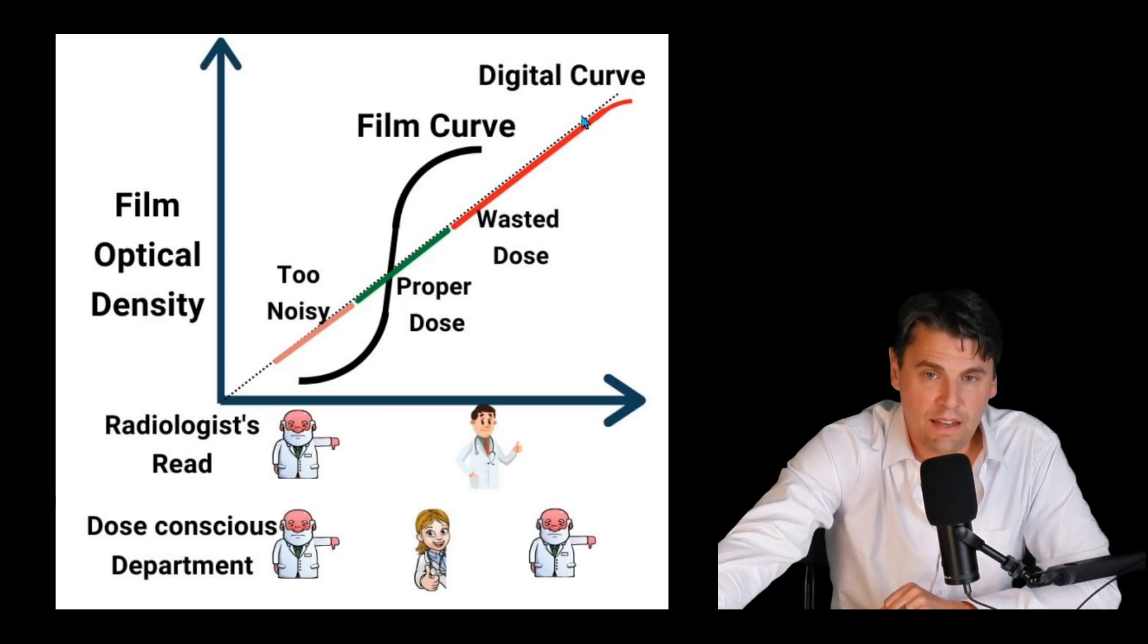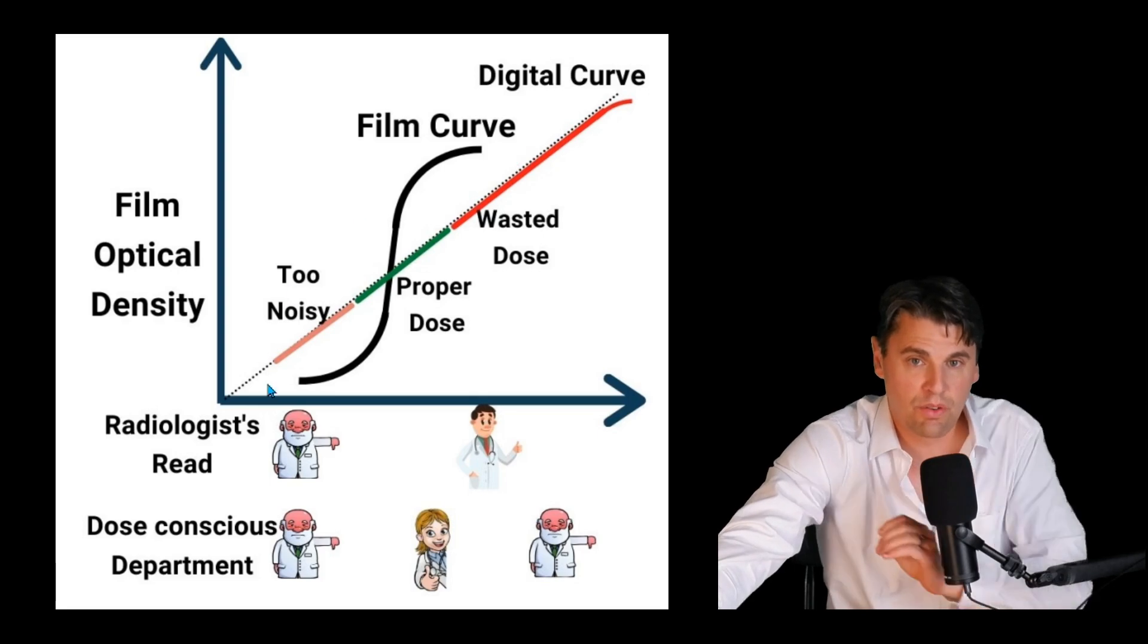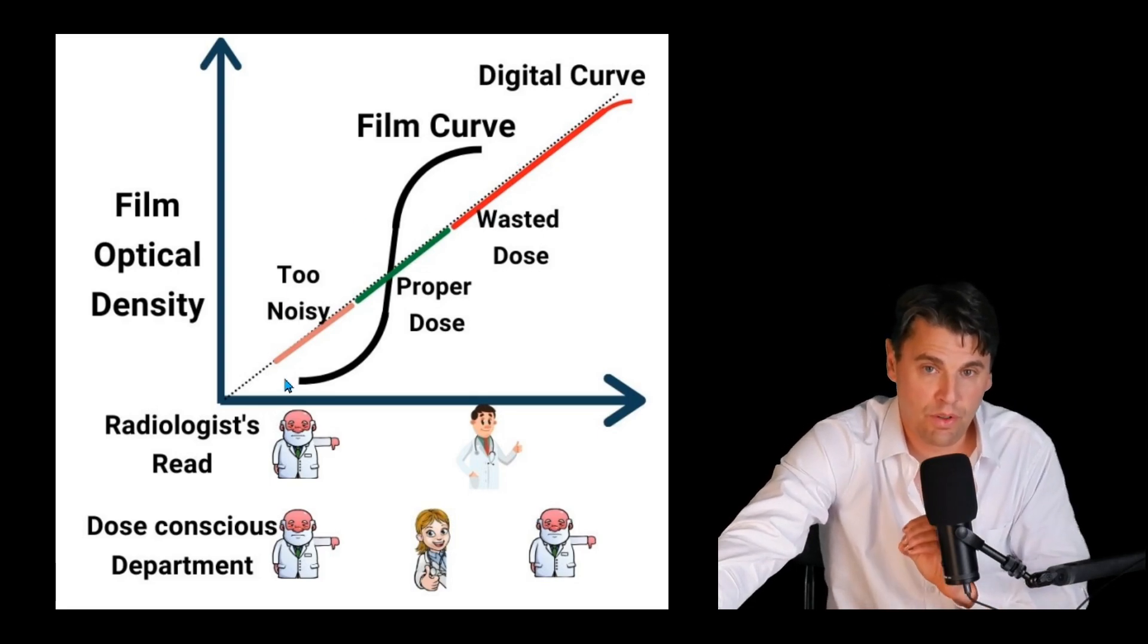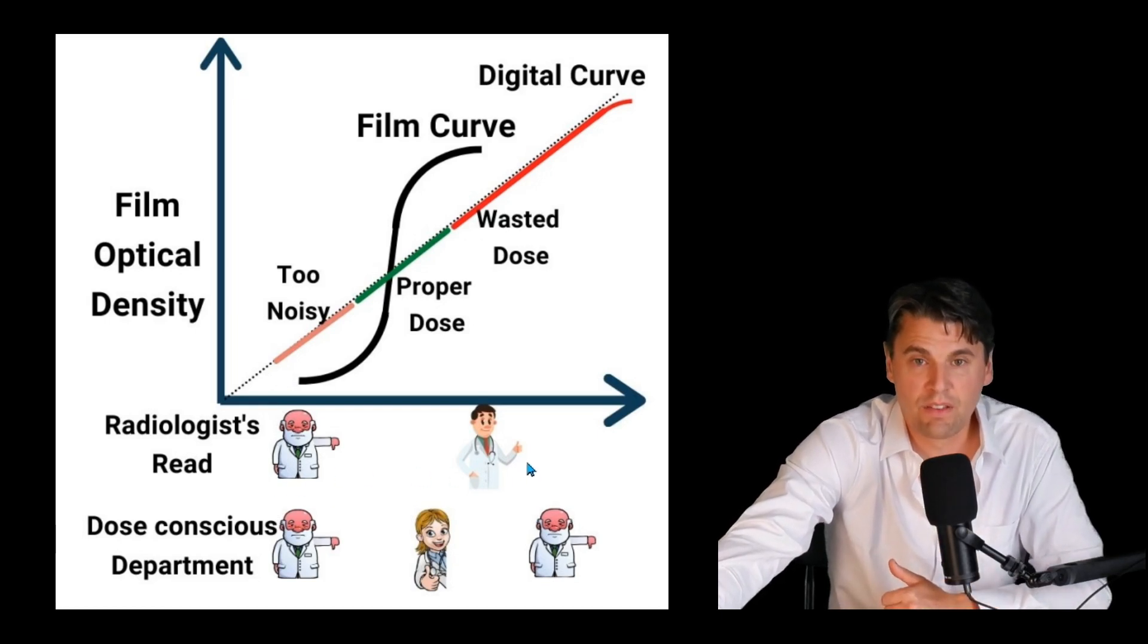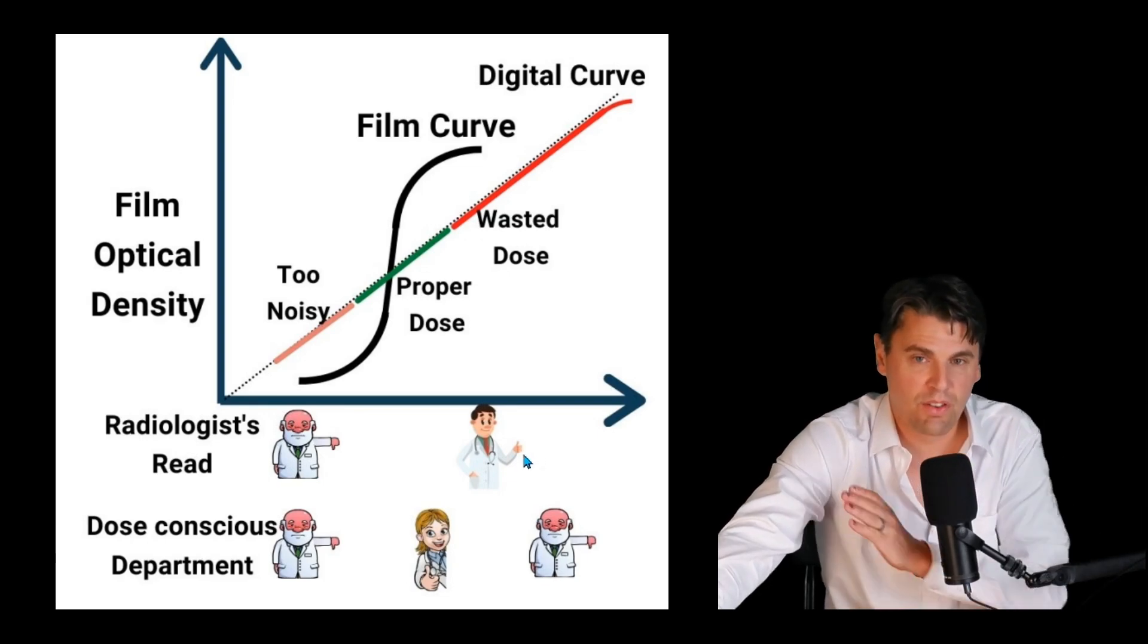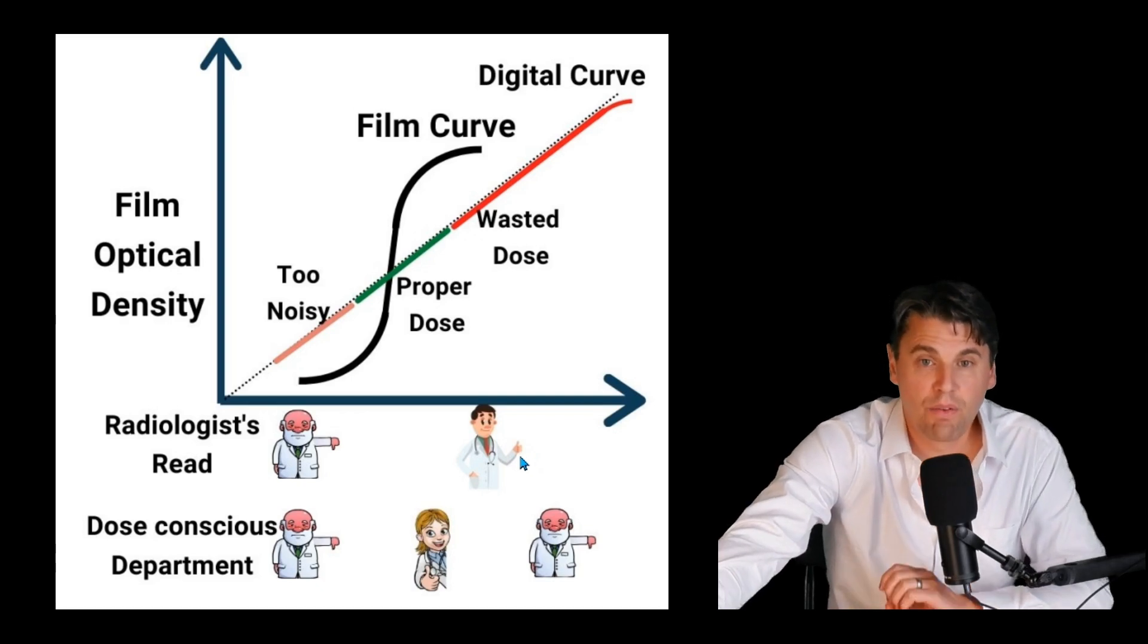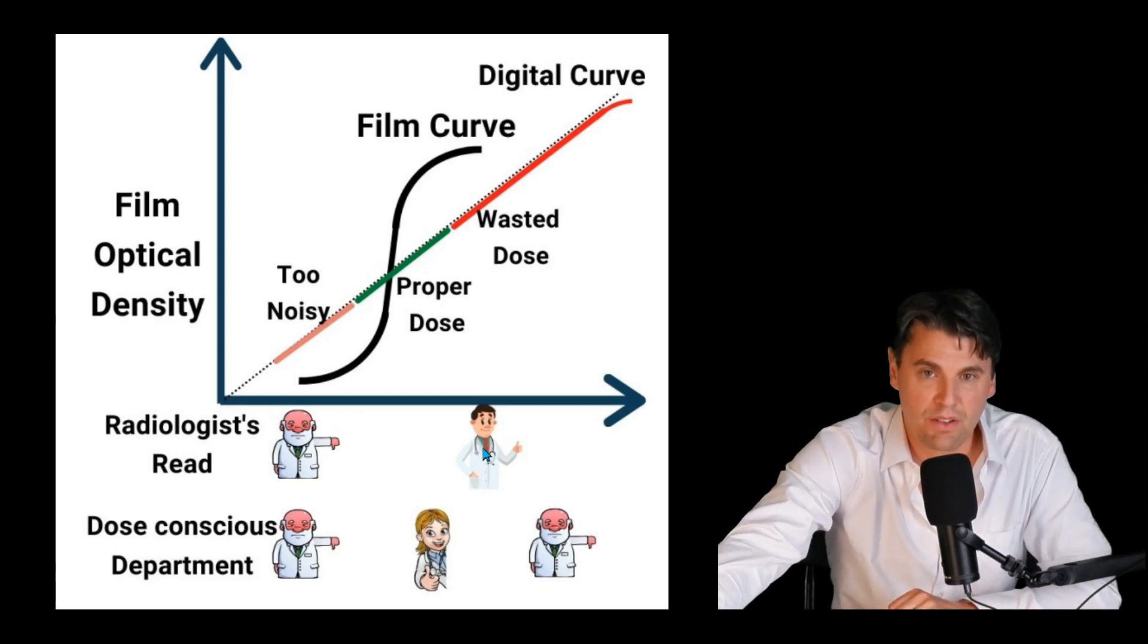We call this linear because it's basically just a line. It means we have a linear relationship between the actual intensity that we're measuring at the image receptor and the dose that was imparted at that image receptor or the exposure at the image receptor. This nice straight line is great because you can actually make good images at higher doses or lower doses.